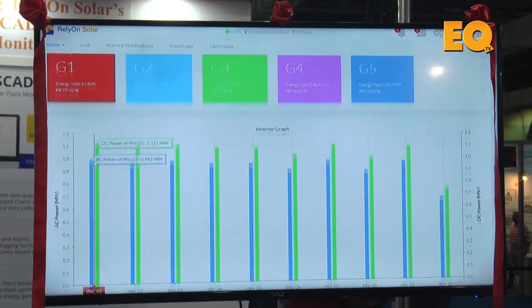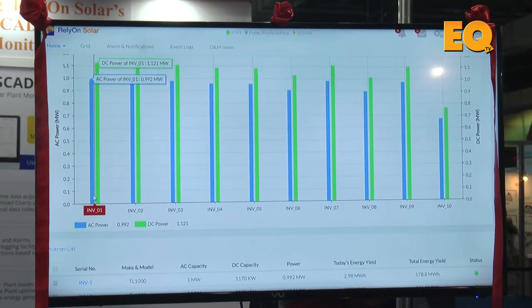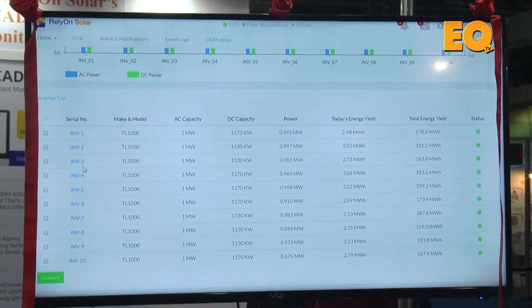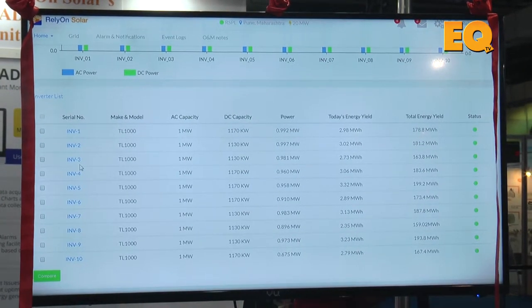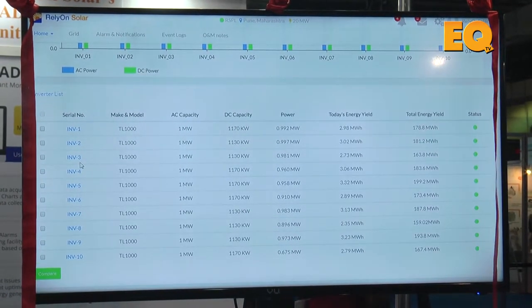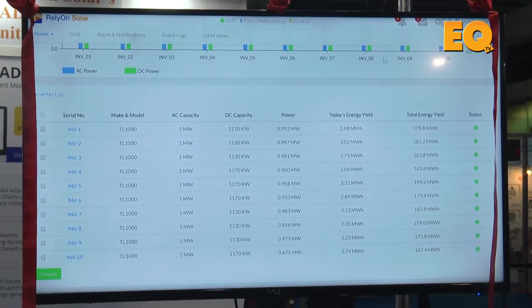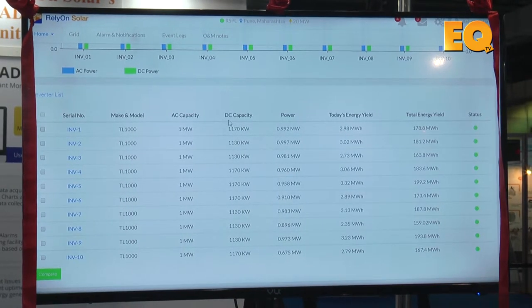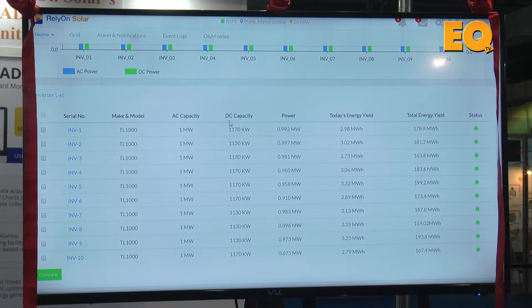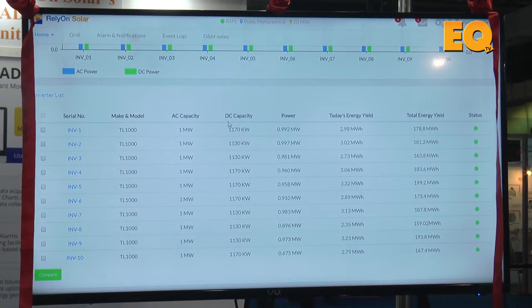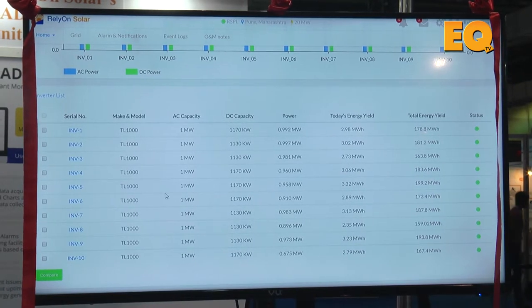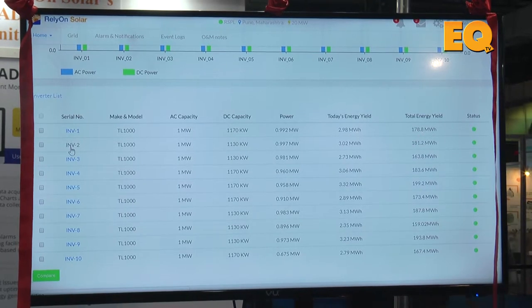Different strings are connected to the inverter. There are a total of 10 inverters in the plant, and these are the different parameters we are monitoring. Whenever DC capacity or power fluctuates or goes below the safety level, alarms and notifications will be sent. Even emails and messages will be sent to the customer. This will help reduce the downtime of the plant greatly and improve its efficiency. For example, I will show you — if we click on the inverter...